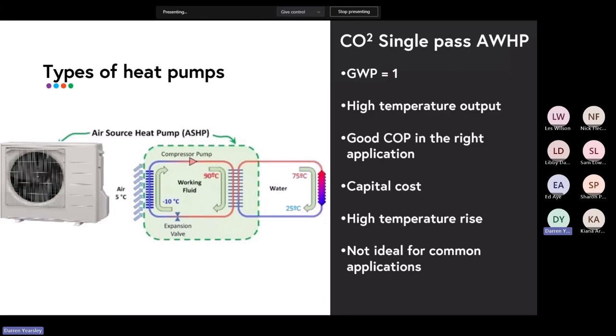Now, single pass. So what does it mean to be a single pass? What it means is across the heat exchanger inside the outdoor unit, it's looking for a very big delta T. So to get a good COP out of these appliances, typically they target a 50-degree difference. So if you've got 20-degree water coming from your hot water system, it raises it up by a 50-degree rise and then returns it to the hot water system at 70 degrees. That has some challenges.